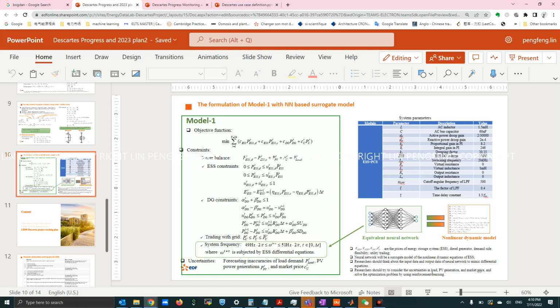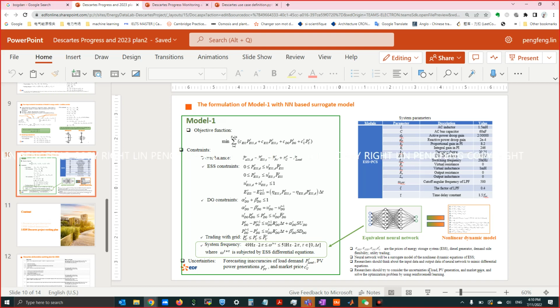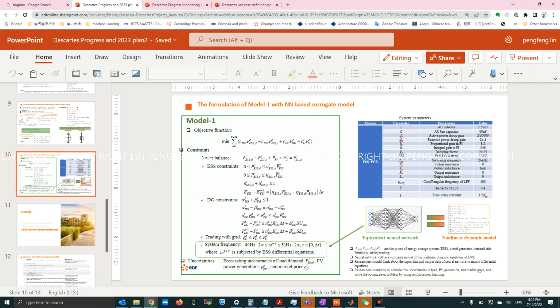Milliseconds, honestly, for primary control, it doesn't make sense. And it even introduces instabilities if you make it on milliseconds. So the ideal is actually to fit within 30 seconds for primary control. This is just to give the boost for reacting in front of any disturbance, imbalance, whatever. That's 30 seconds, 10 seconds, that's good.